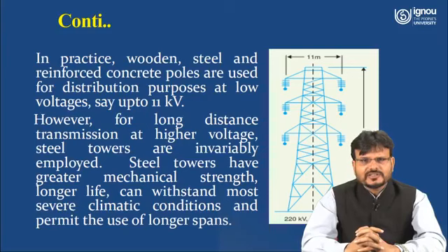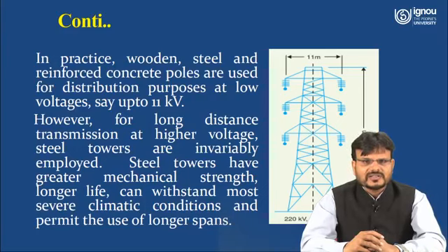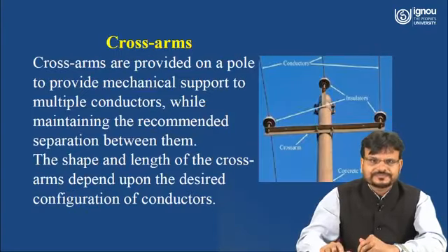In practice, wooden, steel and reinforced concrete poles are used for distribution purposes at low voltage, say up to 11 kV. If you want to use more than 11 kV, like 33 kV, 220 kV or 765 kV for transmission, then such long towers are used. However, for long distance transmission at higher voltage, steel towers are invariably employed. Steel towers have greater mechanical strength in comparison to the rest of the poles. They have longer life, can withstand the most severe climatic conditions and permit the use of longer spans.